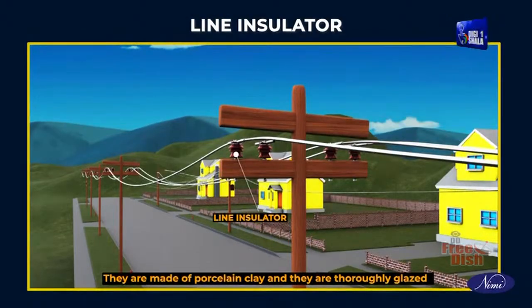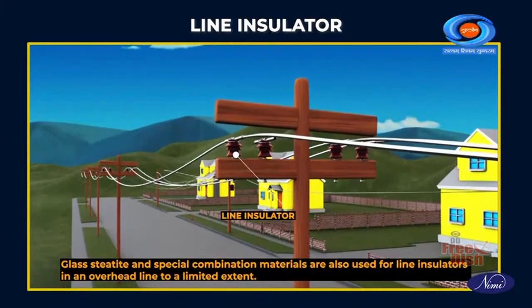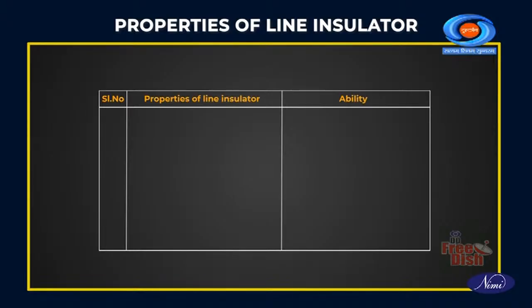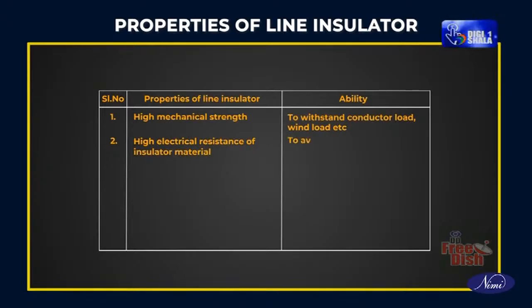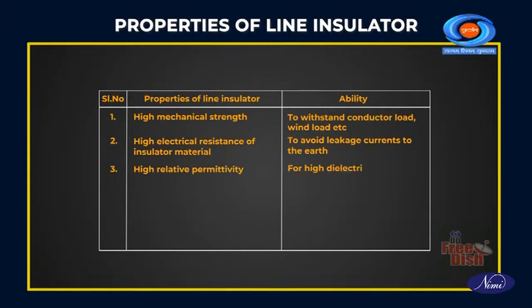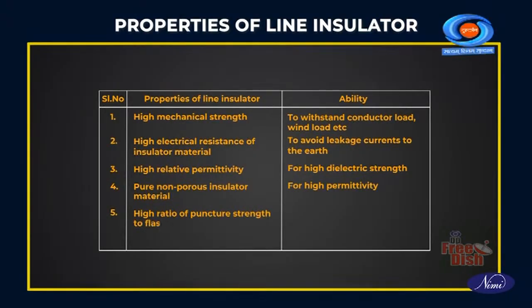They are made of porcelain clay and are thoroughly glazed to avoid absorption of moisture from the atmosphere. Glass, steatite and special combination materials are also used for line insulators in an overhead line to a limited extent. Properties of line insulator: high mechanical strength to withstand conductor load, wind load, etc. High electrical resistance of insulator material to avoid leakage currents to the earth. High relative permittivity for high dielectric strength. Pure non-porous insulator material for high permittivity. High ratio of puncture strength to flash over, to withstand flash over voltages.